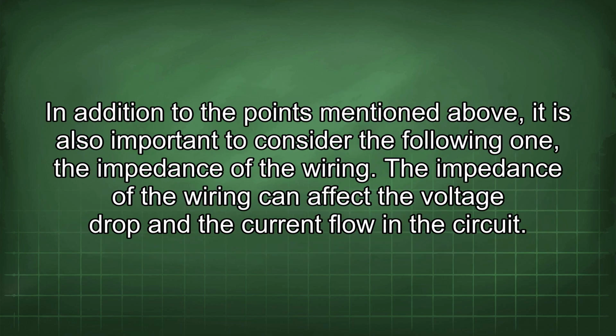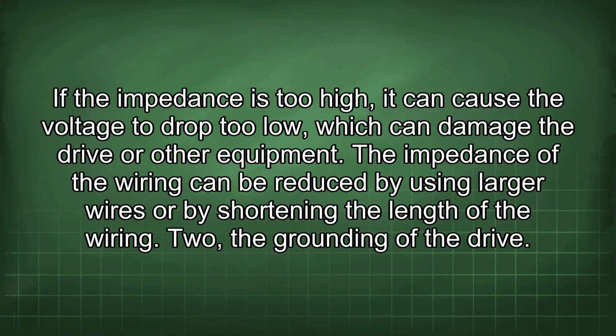In addition to the points mentioned above, it is also important to consider the following. One: the impedance of the wiring. The impedance of the wiring can affect the voltage drop and the current flow in the circuit. If the impedance is too high, it can cause the voltage to drop too low, which can damage the drive or other equipment. The impedance of the wiring can be reduced by using larger wires or by shortening the length of the wiring. Two: the grounding of the drive.